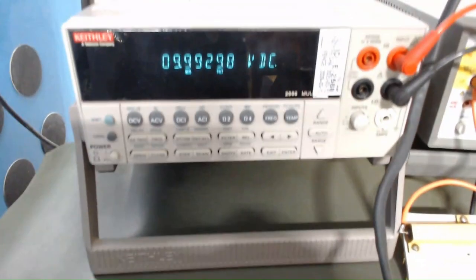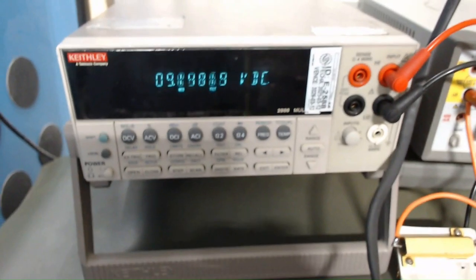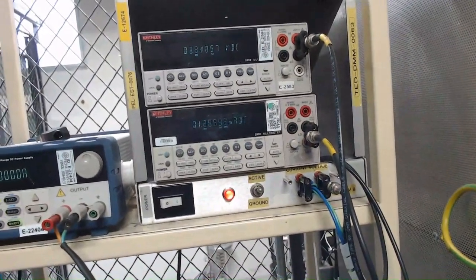Also, we will monitor the output voltage programming test point in the fixture that is connected directly to pin 7 of the 15-pin connector. You will see that programming voltage as well as output voltage are at max rated value, since the output is at 50 kV. The potentiometer will be decreased to minimum, which is 0 volts. Presets will be recorded in the datasheet.